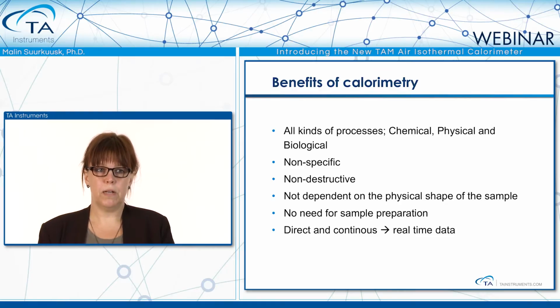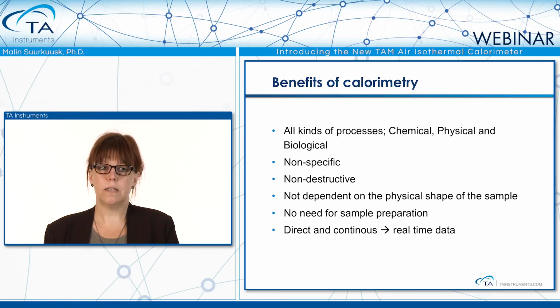It is not depending on the physical shape of the sample. Anything you can fit into our sample handling ampules could be put into the calorimeter. There is no need for sample preparation, but of course you could do if you need to have more specific measurements, but you can just load your sample into the calorimeter and measure the heat output. It's direct and continuous, which means that you get real-time data and not snapshots over the time.